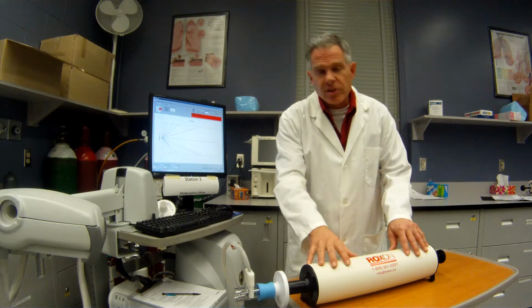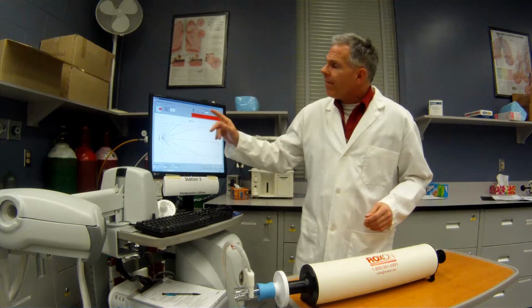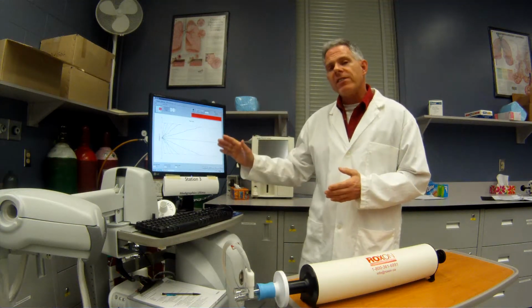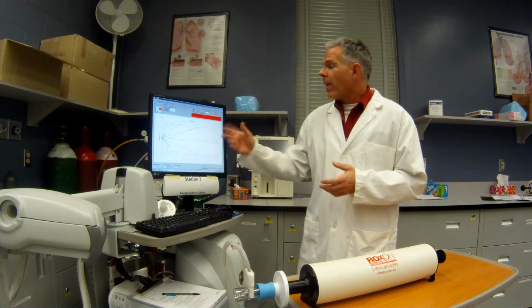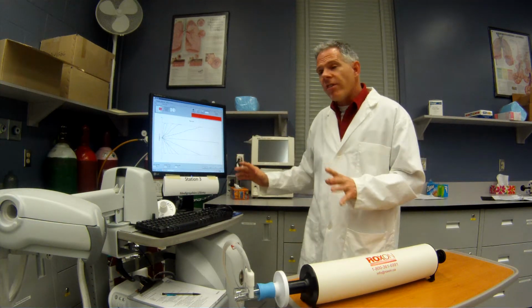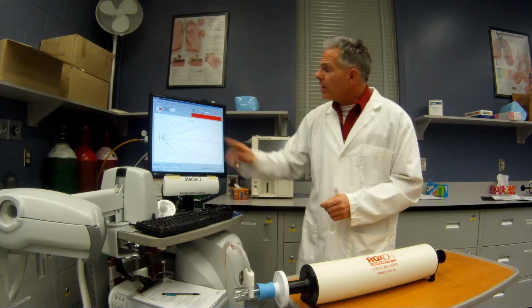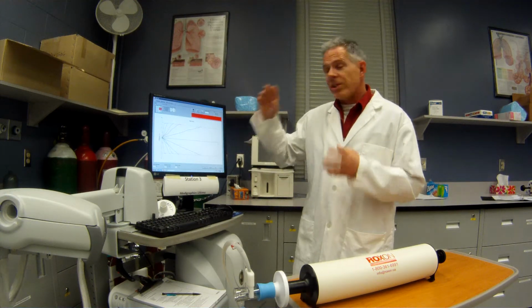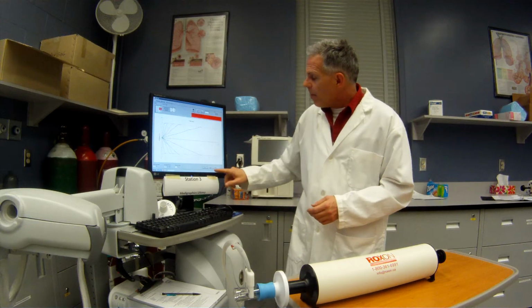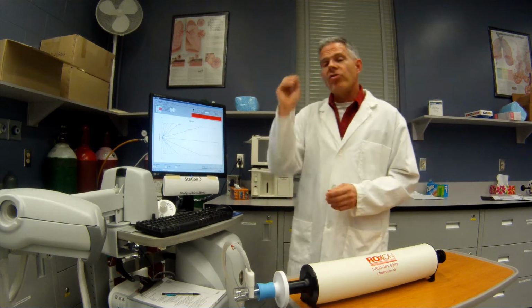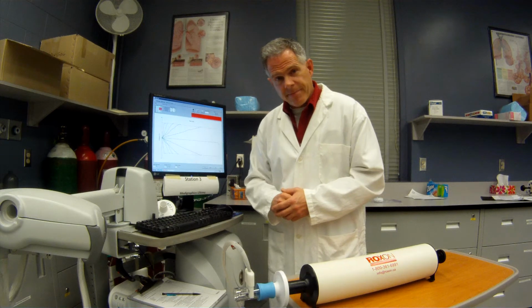So on a 3-liter syringe, that's 90 mils. That's actually quite a bit. You'll find out that these devices calibrate much closer than that. In fact, these ones calibrate to within less than 1% error. So that's basically an orientation to the device and how you calibrate. You might have to repeat this a couple of times until you get a calibration pass. Then we print up the report, and you'd sign it off as being calibrated and verified, ready for use for the day. Thank you very much.